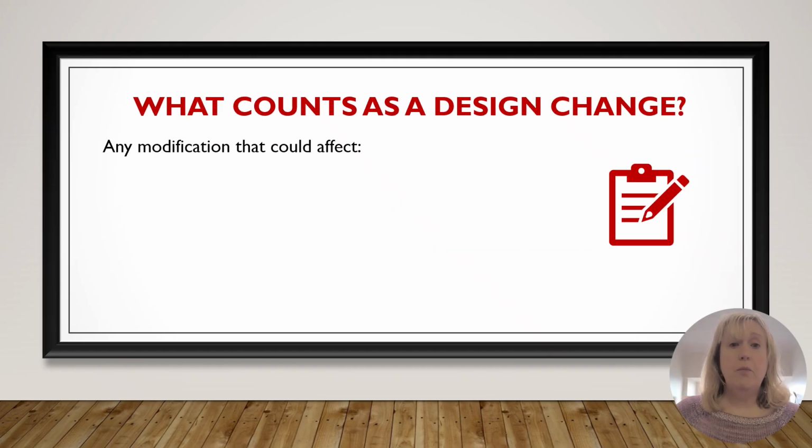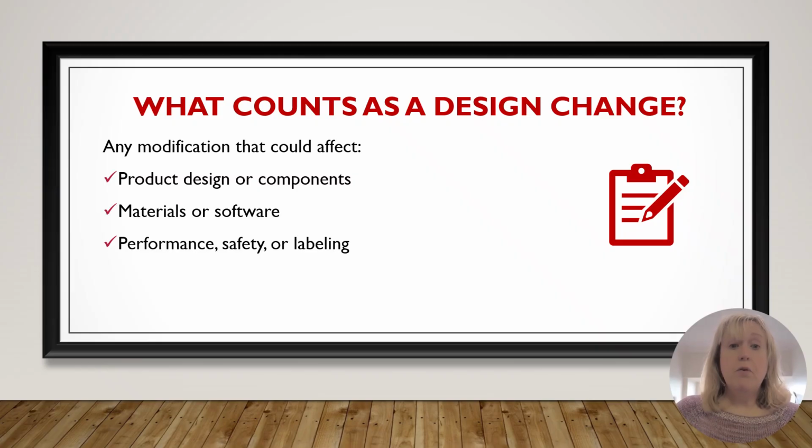A design change is broader than what most people think. It's not just about redesigning a circuit board or changing software code. Even something like switching materials, updating labeling, or tweaking a performance parameter can count as a design change, especially if it impacts safety or performance.